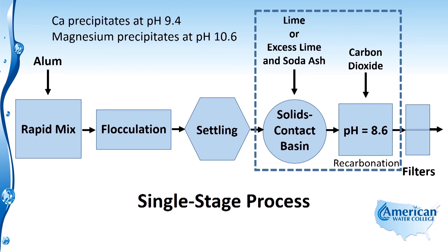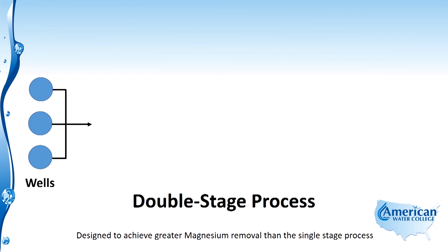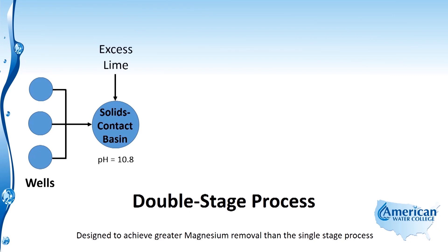Now we'll look at the double stage process. For this example, groundwater from multiple wells that is too hard is sent to a treatment plant for double stage processing. In the first stage, the water is sent to a solids contact basin where excess lime is added. Because we're trying to remove magnesium, extra lime is added to raise the pH to 10.8 — anywhere over 10.6 — to get the magnesium to precipitate out.